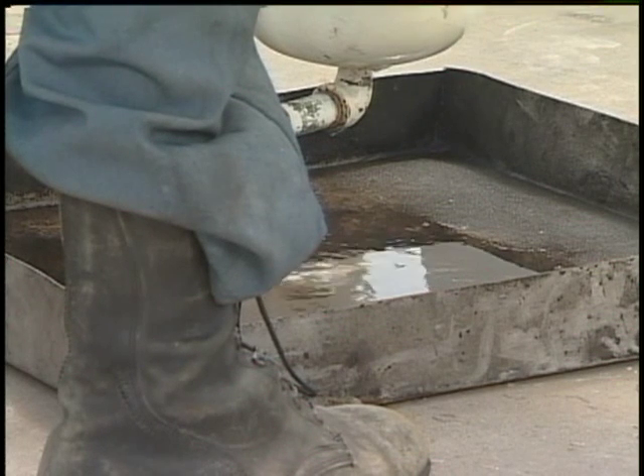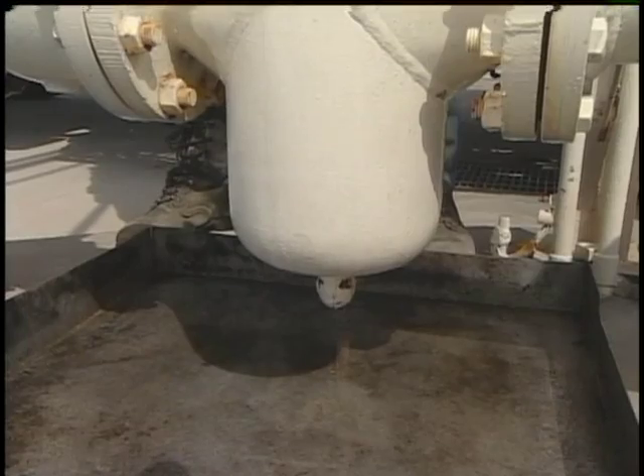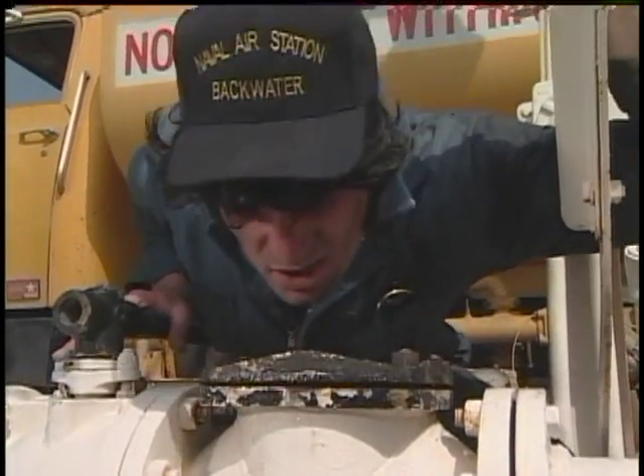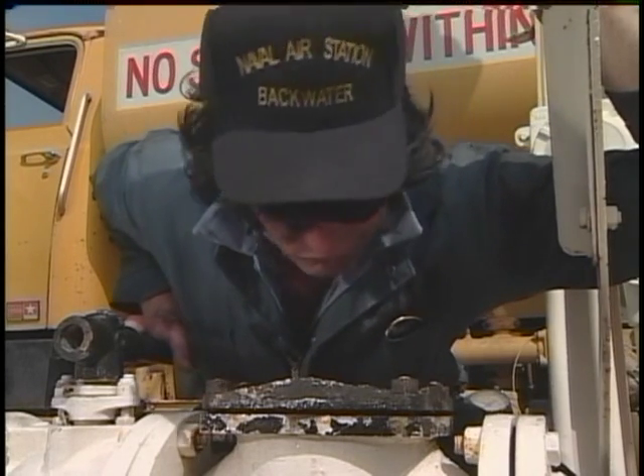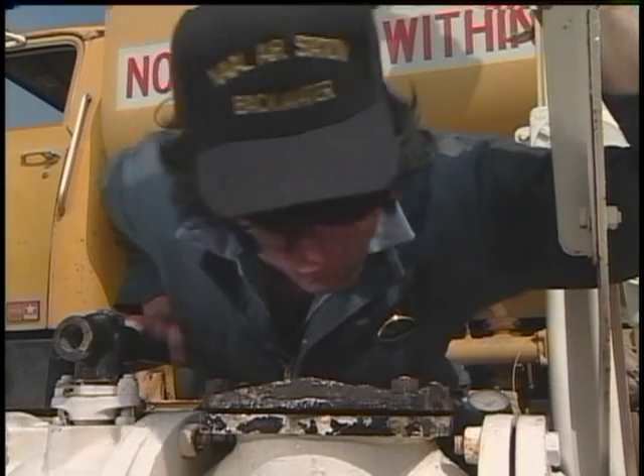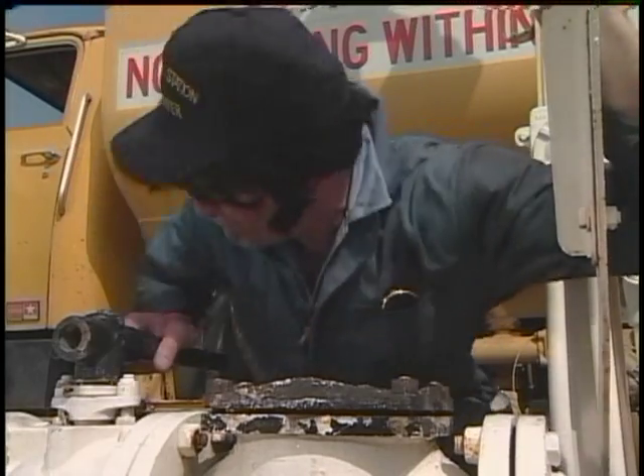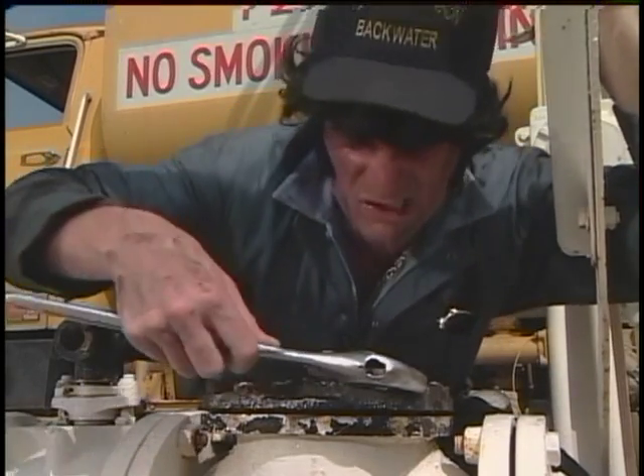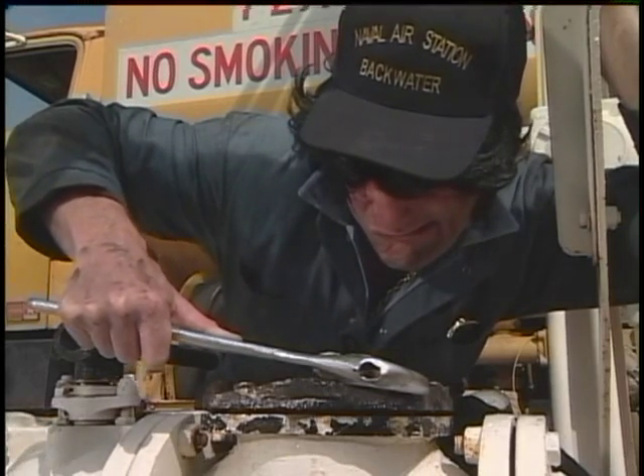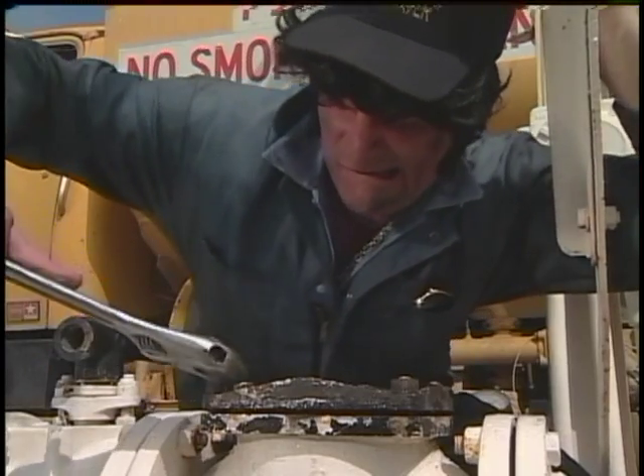Here's another common type of spill — the simple drip from a seal. I'll fix that thing someday. You ought to fix that thing today, Elvis. Drips add up: a single drop per minute will spill 40 gallons a year. That fitting is dripping about once every five seconds — twelve drops a minute — that's about 500 gallons a year. Elvis wouldn't think of emptying a 500 gallon tank onto the ground, but that's essentially what he's doing.